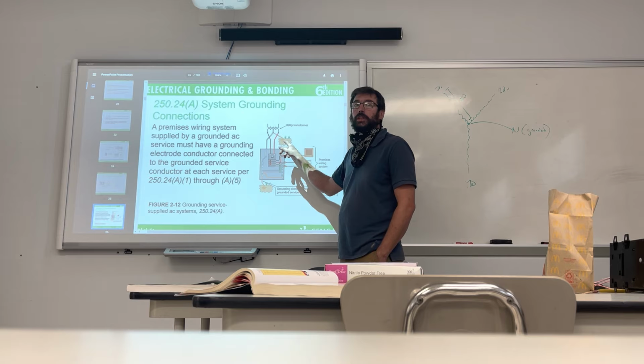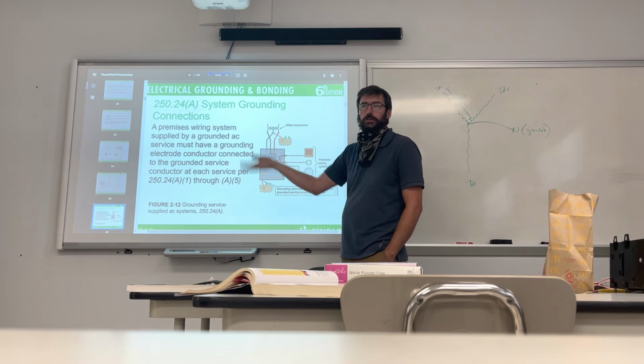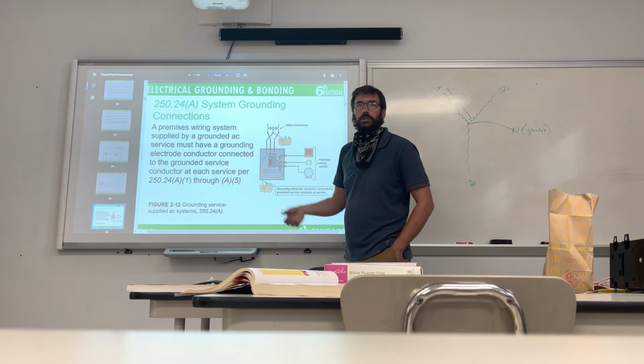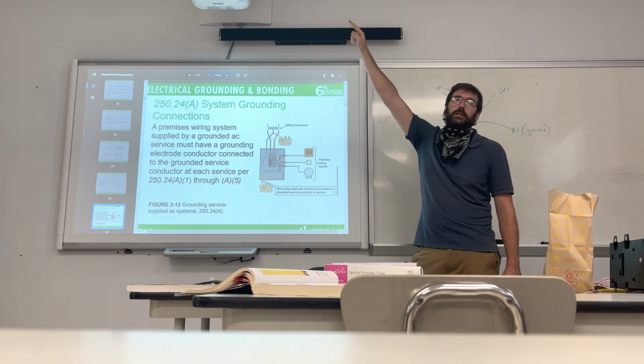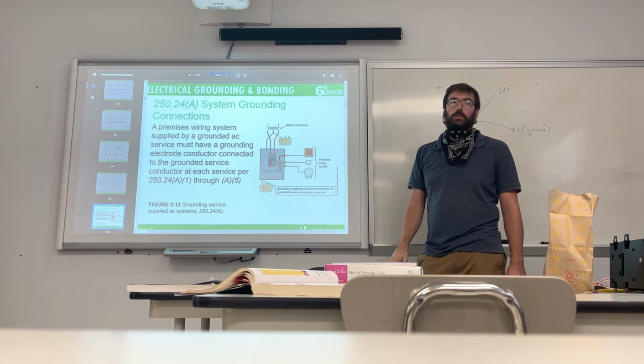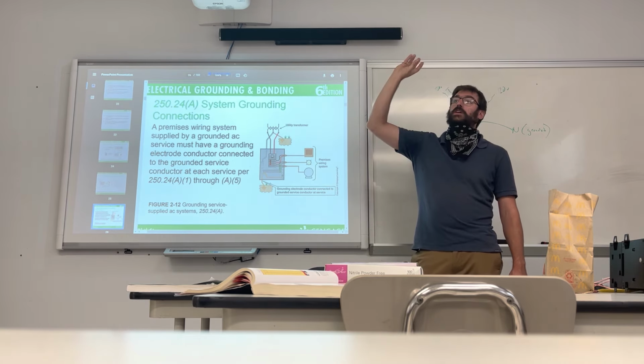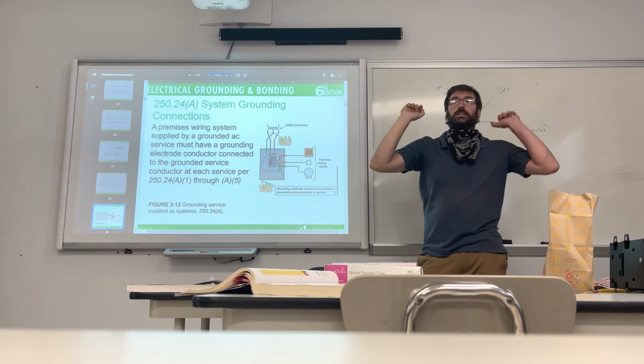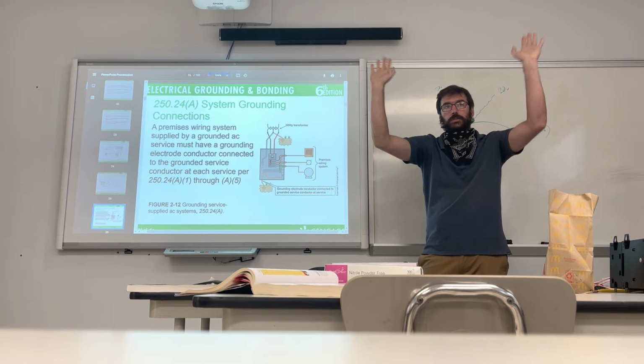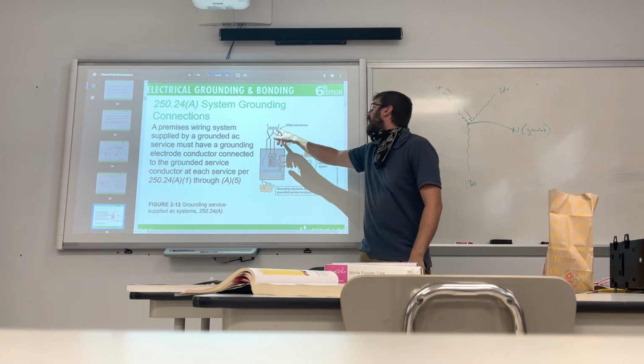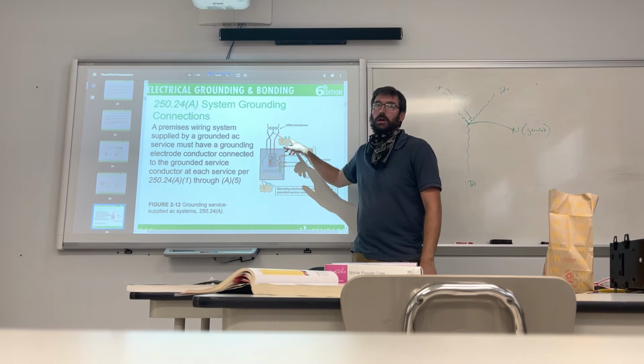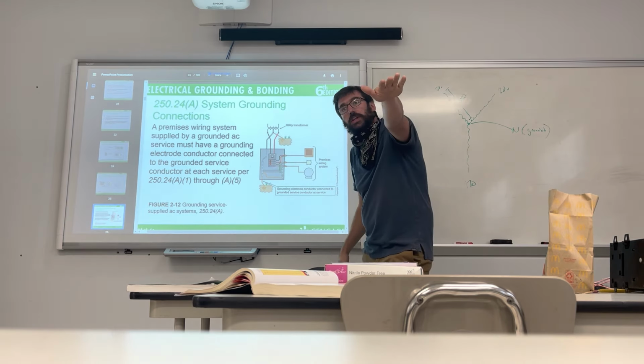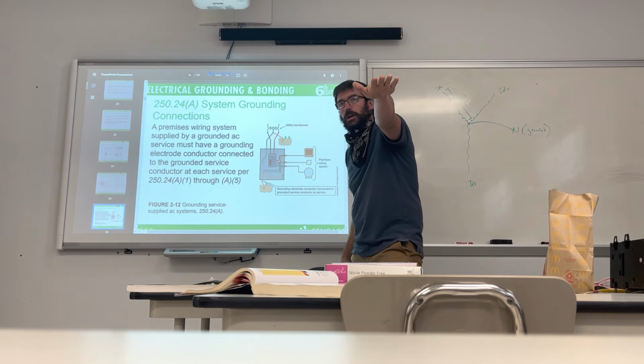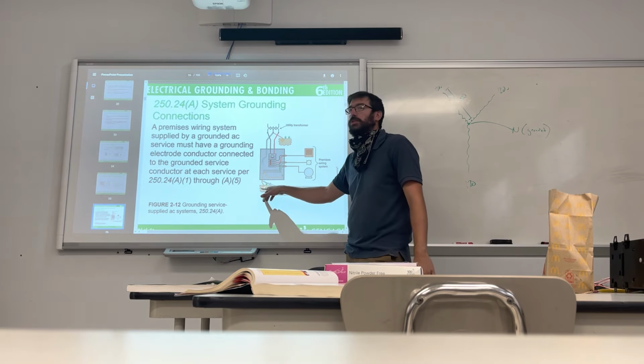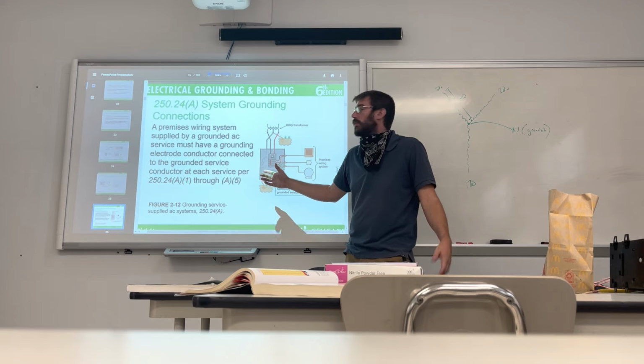Are you ever going to have to deal with that? No, that's the utility's. We don't deal with that. We're only concerned with what touches our weatherhead and down. That's all we own. From the wires connecting to the weatherhead out to the street, that's all the utility's. It's all theirs. So they ground that transformer. When they're sending that neutral over to you, that neutral is already a grounded conductor. So you just have to make sure you ground it once again, because that's what we have to do, that's the law.